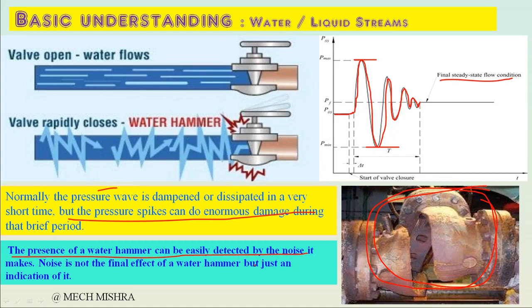Normally the pressure wave is dampened or dissipated in a very short time, but the pressure spike can do enormous damage during this brief time. This spike is very sudden, but it can damage my piping system and lead to catastrophic failure of the piping system. The presence of water hammer can be easily detected by noise. The noise is not the final effect of water hammer but just an indication of it. So if you are hearing lots of noise in your piping system, it means your piping system is suffering from this water hammer issue. So you have to be cautious, right?